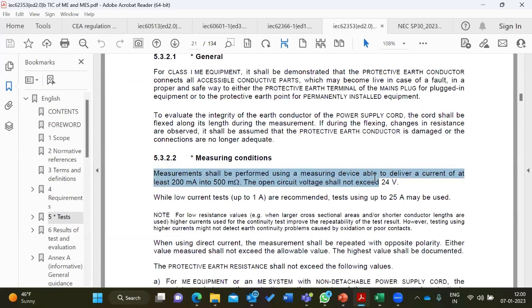Measurement shall be performed using a measuring device able to deliver a current of at least 200 milliampere at 500 milliohm. The open circuit voltage shall not exceed 24 volt. While low current tests up to 1 ampere are recommended, tests using up to 25 amps may be used.